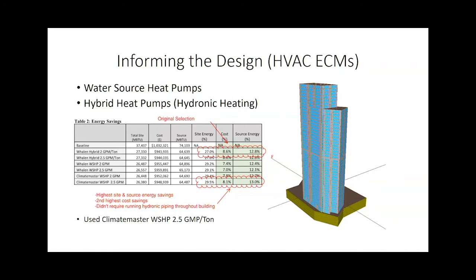So we looked at six options for this one. On this table, we've got site energy, energy cost, source energy, and then percent site energy savings, percent cost savings, and percent source energy savings. And for this one, again, we have the baseline, which was just the code compliant version of the building, and then these six options. So we looked at a couple of the hybrid systems and then four of the traditional water source heat pump systems.